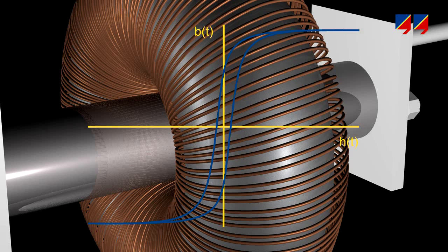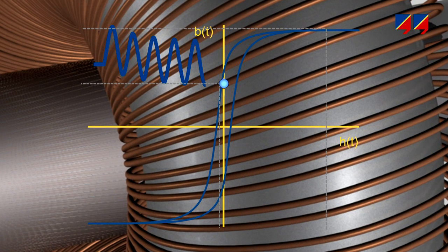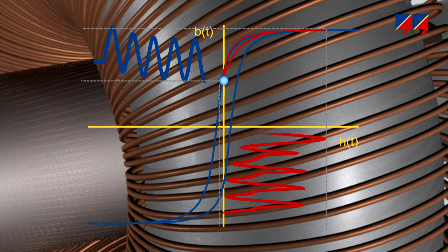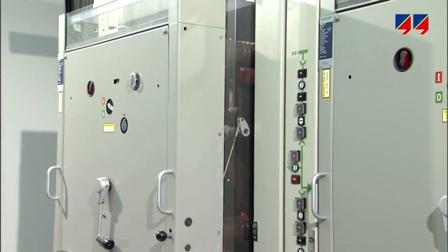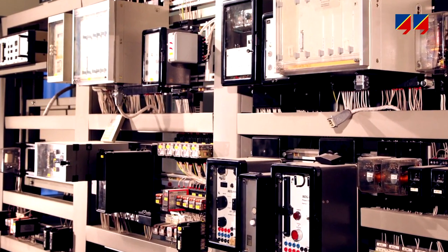During a fault, the accumulated remanence will allow a much lower fault current to saturate the CT. The higher the remanence, the lower the fault current required to drive the CT into saturation, which might subsequently cause a maloperation of the protection system.